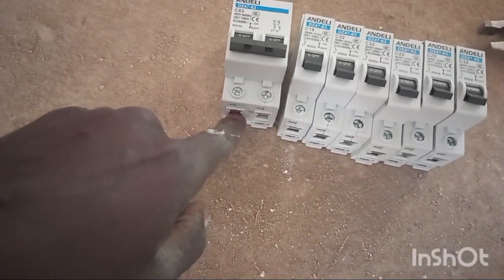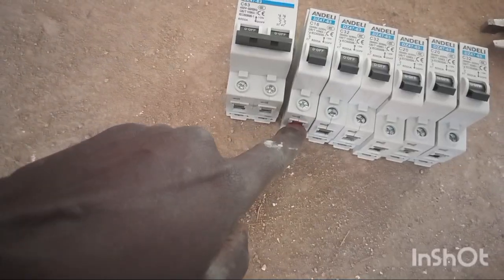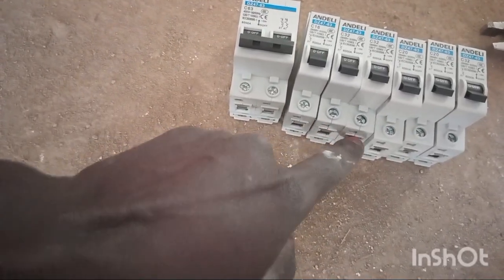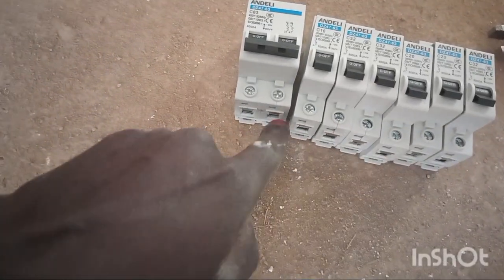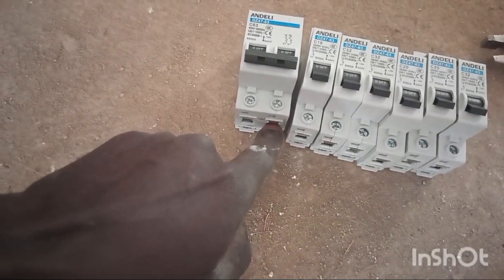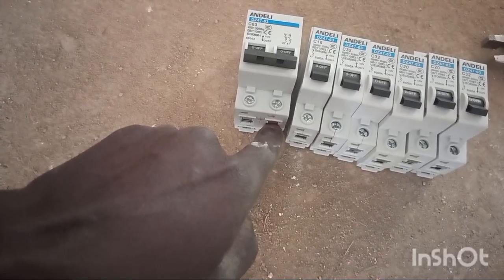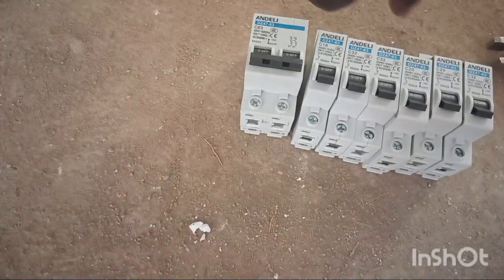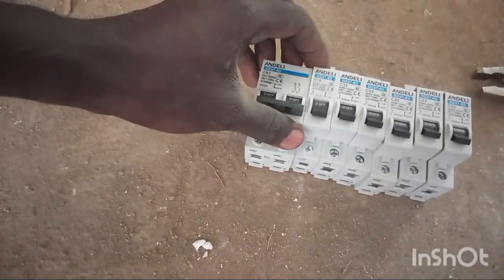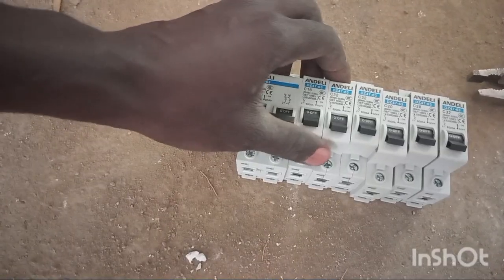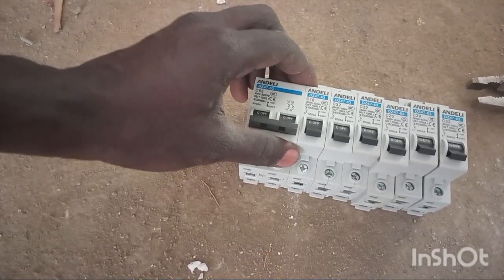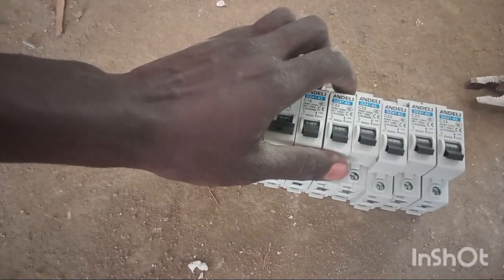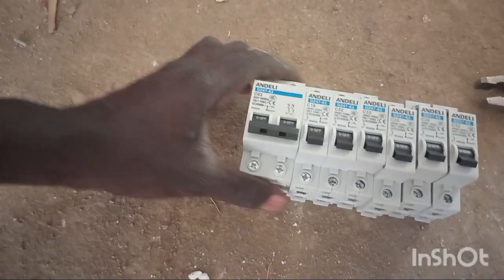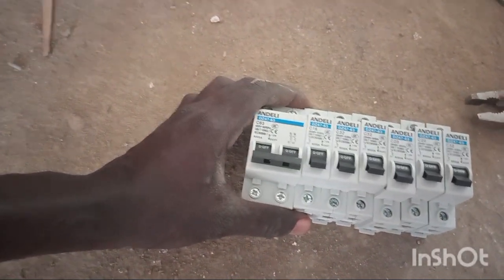Then from the main, we loop them to the circuit breakers. We loop the phase to all circuit breakers using a connector. Then for the neutral, we loop with a wire from the neutral here to the neutral bar in the consumer. We are going to take a loop from here to the neutral bar, then the green cable for earthing. The green cable will be connected to the earthing bar also in the consumer unit. So that's, for example, how we are going to arrange our consumer.